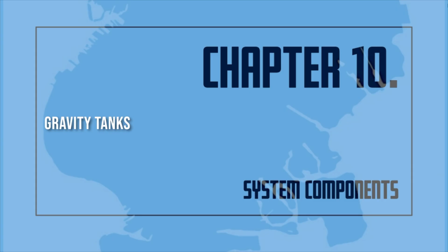Severe damage can occur to the piping and the tank if the water inside the tank freezes. During freezing weather, the temperature of the water inside the tank and the riser must be checked daily. The temperature of the water shall always be at least 40 degrees Fahrenheit. Ice should not be allowed to build up on the gravity tank. The extra weight of the ice might weaken the supports of the tank and cause the tank to collapse. Falling icicles may also cause damage or injury. It is essential to be sure that the tank is properly heated, insulated, and carefully maintained.